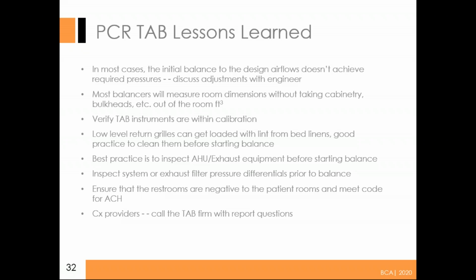A lot of times in isolation rooms, low level exhaust, especially when you're going in to re-verify, a lot of times here, depending on which hospital, it's every 6 months or every year. Low level exhaust can really be a hindrance, especially with all the linen and so forth like that. One of the first things I've always done when I walked into the room, that was the first place I went, is those low level exhaust. Because a lot of times they're drywall ceilings, you really don't have access to dampers, and they're notorious for putting OBDs or opposed blade dampers behind the grills. And those things do load up. So typically, that was the first thing I did, was go in, pull the grills and clean them.